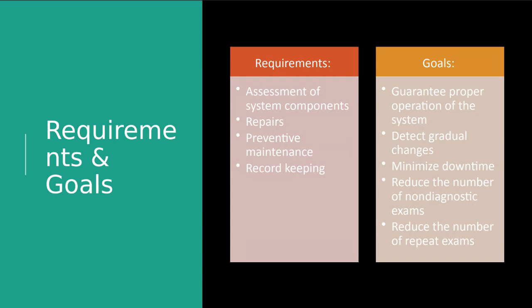Because we're using multi-crystal transducers. If we were using a single crystal transducer, the whole image would be gone, right? So sometimes we don't notice that crystal damage while we're scanning, but someone performing QA could come in and realize that. It's also an opportunity for repairs on the system, preventative maintenance. That's the main thing with QA, making sure that our machine is still staying within the normal functioning range, and record keeping. Like we said, we have to document everything. So the goals of QA: they have to guarantee proper operation of the system, meaning the system and the transducers. They detect gradual changes that, again, we may not be able to notice while we're scanning.